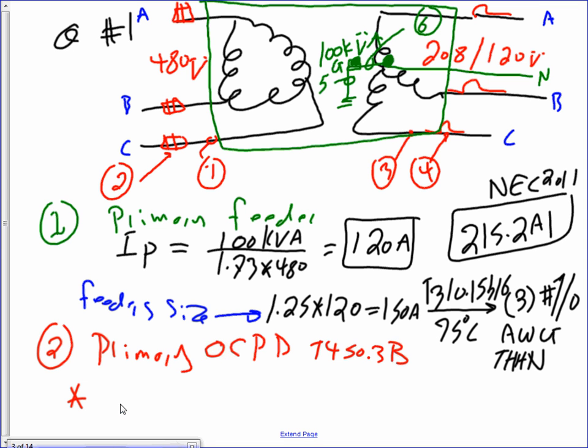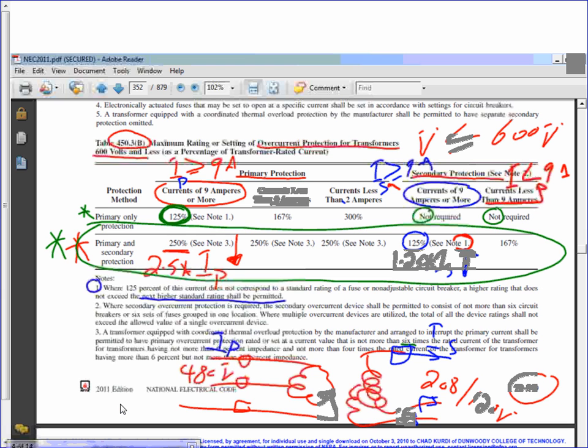Let's go size the fuse. Any comments, any questions, guys? Before we size the fuse, everybody's good? I'm going to take you to this table. This table is directly from table 450.3(B). If you have never been there, grab your code book and highlight it. You need to know how to use it. The most important thing about this table is that it's for overcurrent protection for transformers 600 volts and less. You can use this one only if the transformer is 600 volts and less.